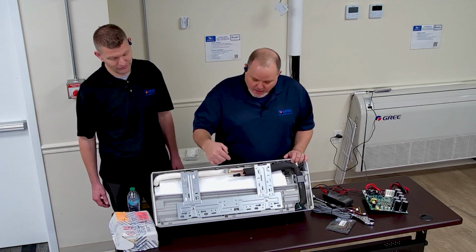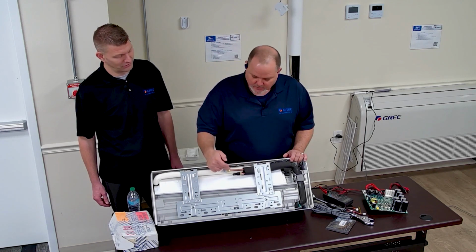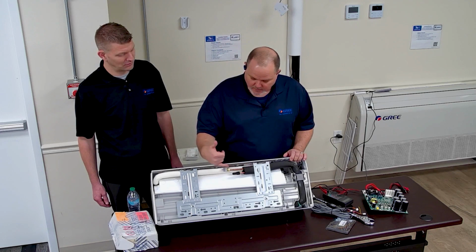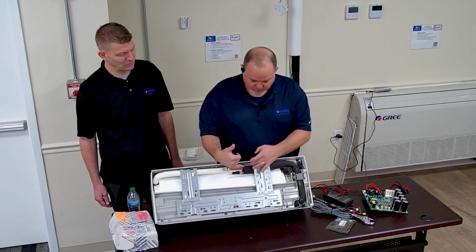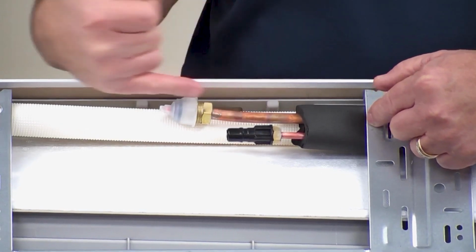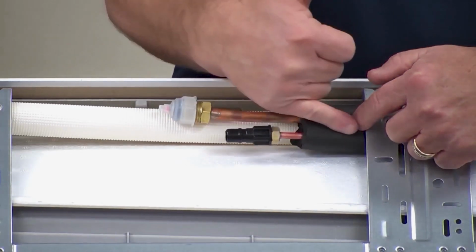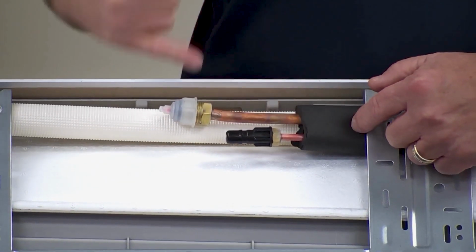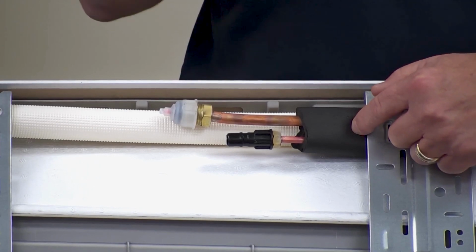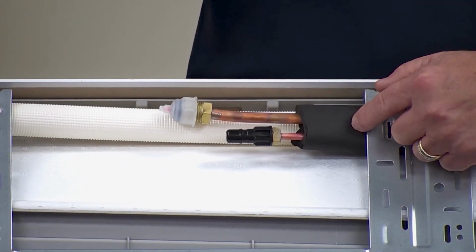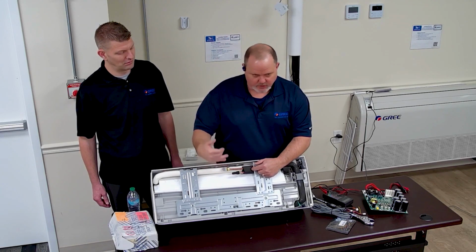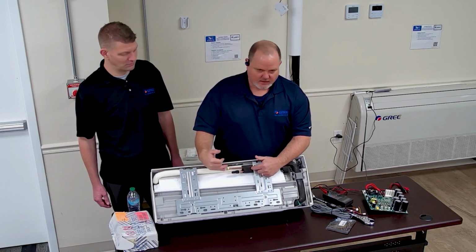Correct. The brazing, I don't want the brazing on the back of these heads for the reasons he was talking about, but also on the GMV wall mount, if you pick that insulation back, there's a strainer here too. And if you're brazing on this head, you could possibly overheat and damage the strainer. So what I tell guys all the time, and we've preached it to the choir with mini splits, and I'm going to preach it again, the manufacturer puts flares on these. They've been doing flares well before I even got into this business.